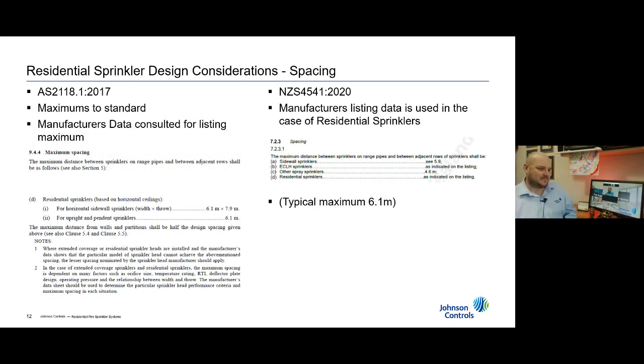When we come to the maximum spacing for residential sprinklers, you'll see that there on the screen, Section 9.4.4 in the Australian standard. It does reference manufacturer's data, but only to say that if the sprinkler you have is only listed to 5.5 meters, then you're only allowed to use it to 5.5 meters, not to the full 6.1 that's in the standard. New Zealand standards are actually a little bit more pragmatic here, I think. Perhaps a bit more sensible, dare I say, and say, look, if a manufacturer's tested it to 7.2, then do it, because that's in the listing. Not that I'm aware that anyone has tested to 7.2, but typically the maximum is going to be 6.1 meters.